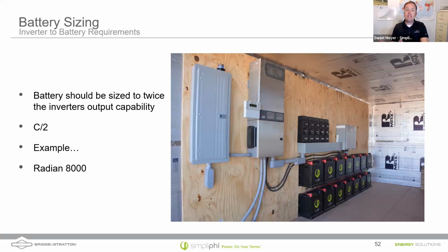Each one of these batteries is 3.8 kilowatt hours. I just said, they can only discharge at C/2. So 3.8 divided by 2 is 1.9. So each one of these batteries that you see in that picture has a max charge or discharge capability of 1,900 watts. So if I have an 8,000 watt Radian divided by 1,900, I get about 4.2. So that means I need about 5 of these batteries so that if ever that Radian starts discharging 8,000 watts to load, you're not going to exceed the maximum continuous discharge capability of the batteries.